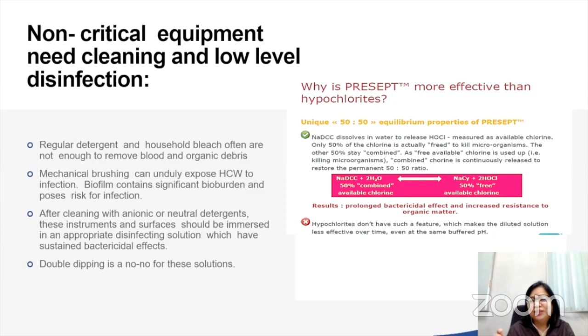So for these wiping solutions, you don't double dip. Double dip is when you've already immersed something in it, then you take that out and immerse something else. That's not acceptable. Semi-critical instruments such as endoscopes and laryngoscopes enter non-sterile body cavities. They need higher levels of disinfection.